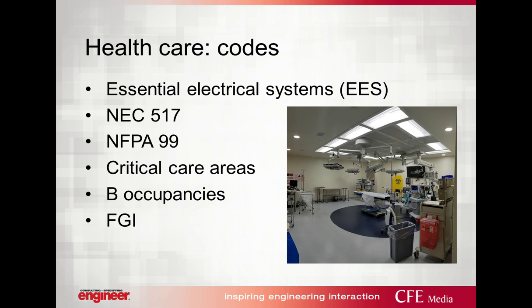Thanks, Rick. If we have a healthcare application, then NFPA 99 and/or the FGI guidelines will be a necessary reference. And in 517.30 in the NEC, we have a requirement for 2 independent sources of power. Now, since the adoption of 2012 NFPA 99 by the CMS and Joint Commission, the facility should perform a risk assessment that determines how the space will be used, who will access the area, if injury is possible with a system failure, and the severity of the injury. This will drive the decision of the category type.